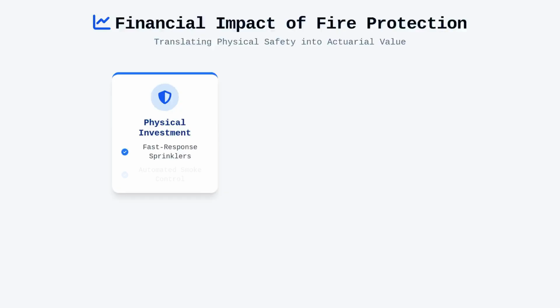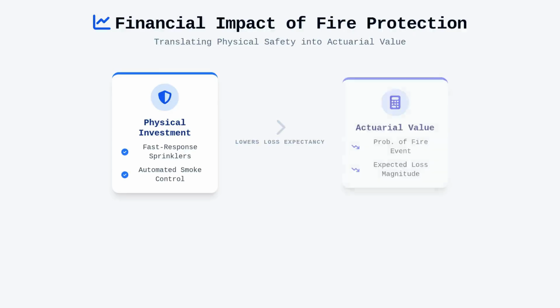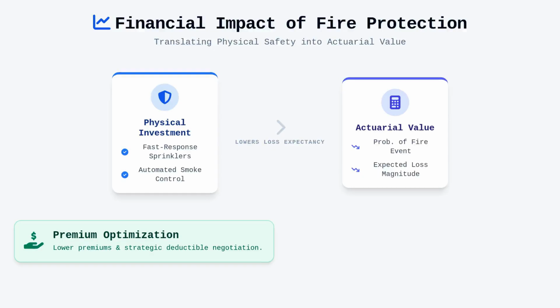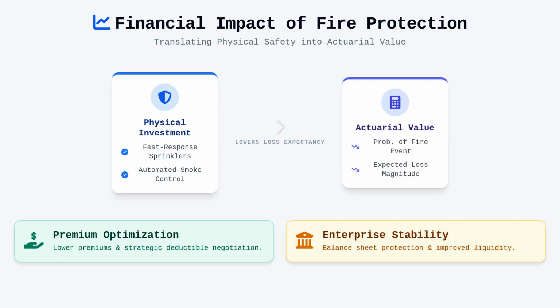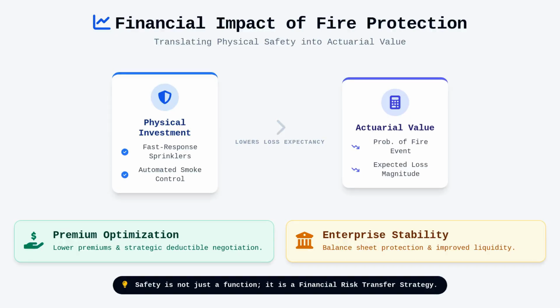When a company invests in advanced fire protection, such as early suppression fast response sprinklers or automated smoke control systems, they are not just performing a safety function. They are actively lowering the enterprise's loss expectancy, which allows for the negotiation of lower premiums or higher deductibles. This, in turn, protects the company's balance sheet and ensures better liquidity in the event of an otherwise devastating business interruption.